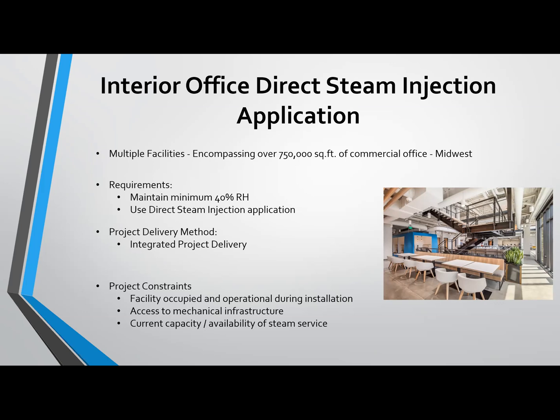Access to the mechanical infrastructure was a fairly large constraint. These facilities weren't old, but they definitely weren't built within the last 20 years. So getting above ceilings, around structure, and around existing utilities added over the years presented a very unique challenge. Some of the ductwork serving these areas is quite large, up to 48-inch square duct in some areas, just because there's so much air that needs to move through these facilities.